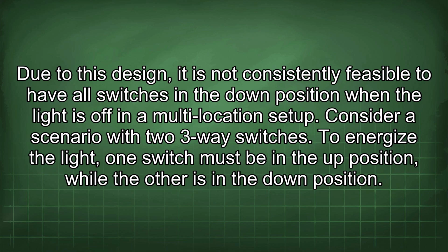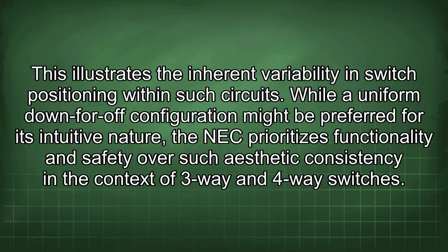Consider a scenario with two 3-way switches. To energize the light, one switch must be in the up position, while the other is in the down position. This illustrates the inherent variability in switch positioning within such circuits. While a uniform down-for-off configuration might be preferred for its intuitive nature, the NEC prioritizes functionality and safety over such aesthetic consistency in the context of 3-way and 4-way switches.